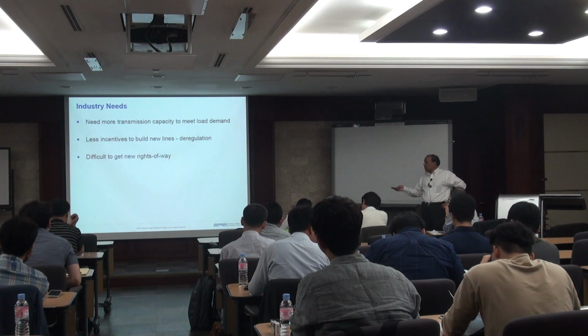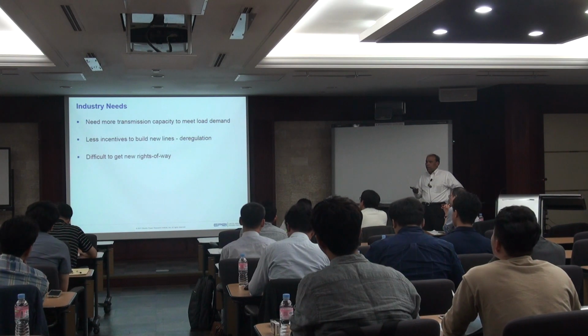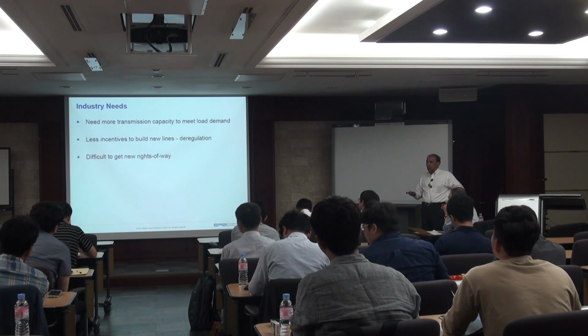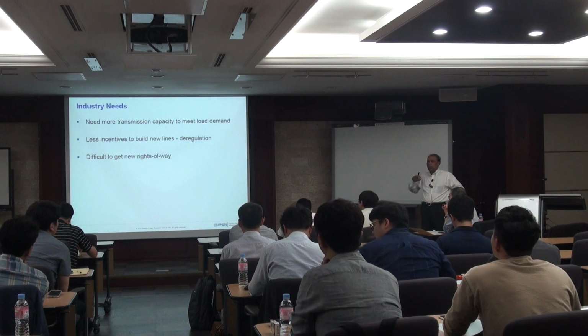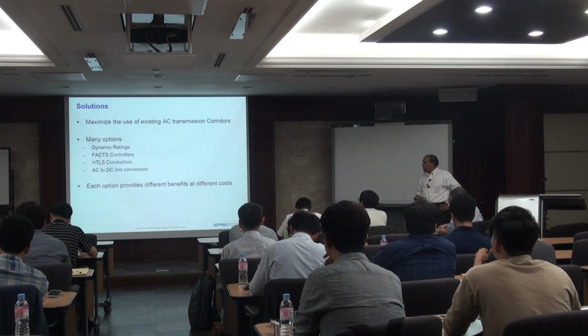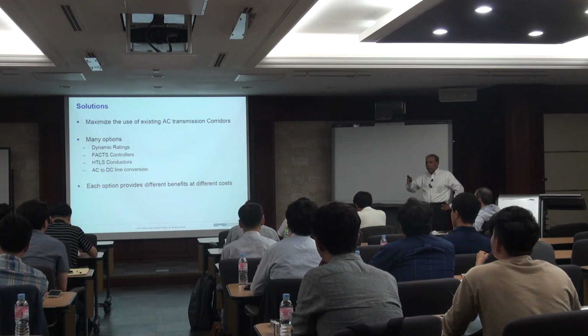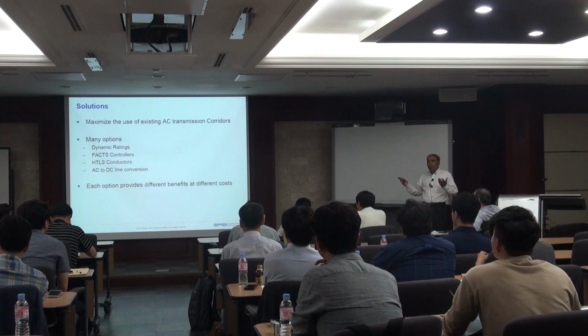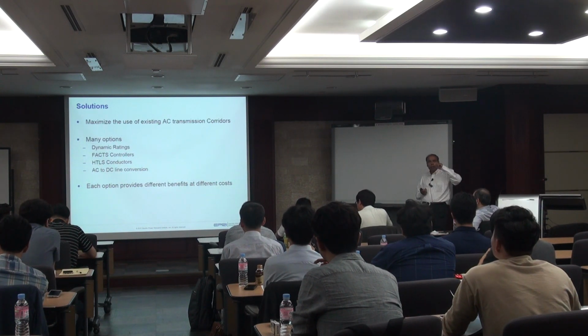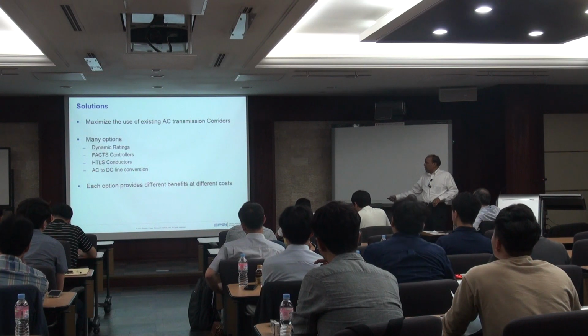I think the industry needs this, because building new lines is difficult and getting new rights of way is difficult. So let's see if we can push more power on the existing AC lines. Before I get into AC line conversion to DC operation, we have a lot of other options you should be aware of to increase power on an existing line. I don't know whether you have heard of dynamic ratings.